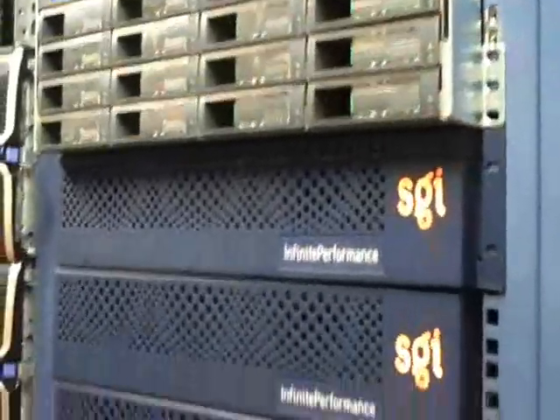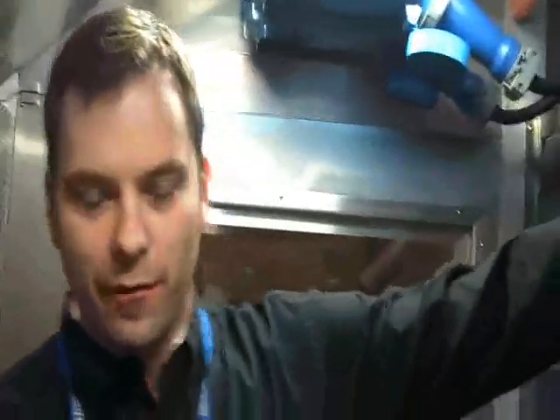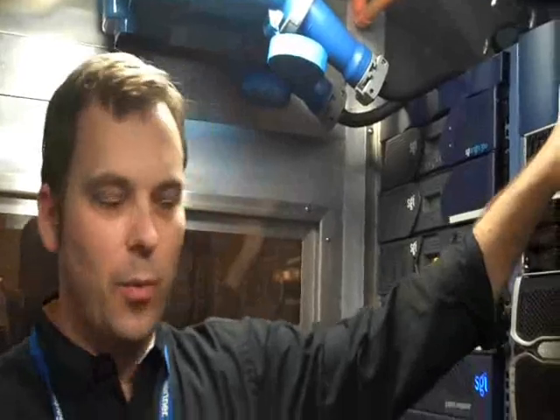So these fans, if you notice them, are actually at an angle, so they're blowing air across this way. These fans are blowing to the left, these fans are blowing to the right. What that does is allow us to do a lot of air mixing, let's put it that way. The air mixing allows us to provide a consistent temperature from the bottom to the top of the rack, depending on the outside temperature. We want to make sure that we have a certain inlet temperature for the servers.